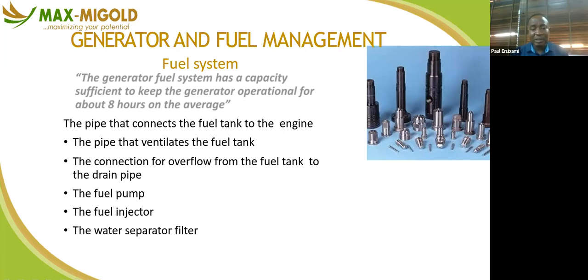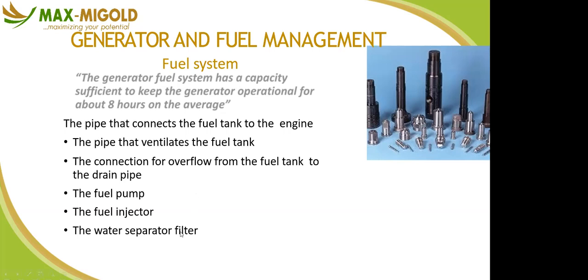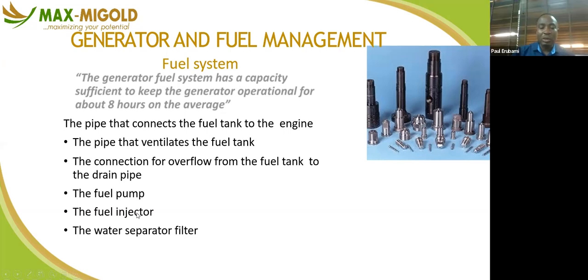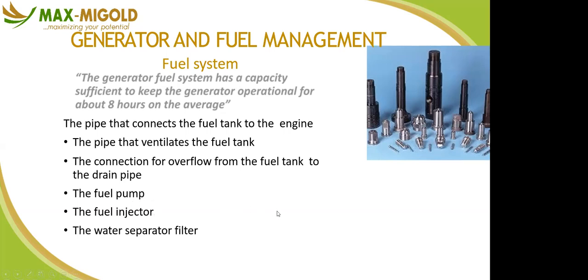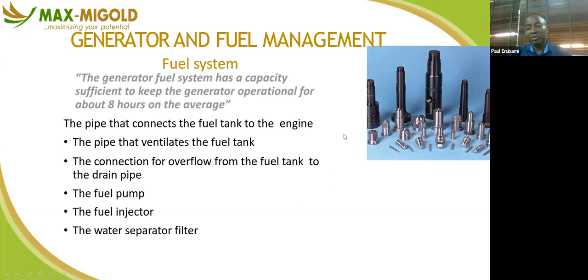If I start it, it starts. But with time, when it's subjected to load, the generator shuts down. You have to check your water separator. It could be your injector because of dirt. Maybe there is an absence of a water separator here. That dirt comes directly to the fuel pump, from the fuel pump to your injector, and starts affecting the performance of your generator.